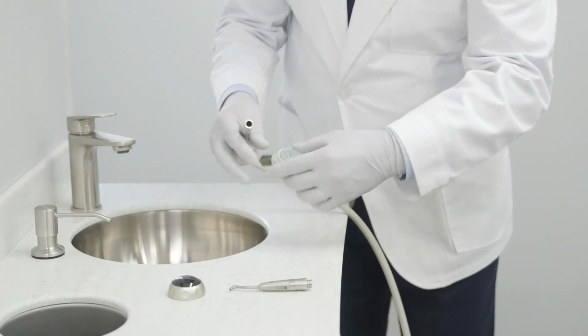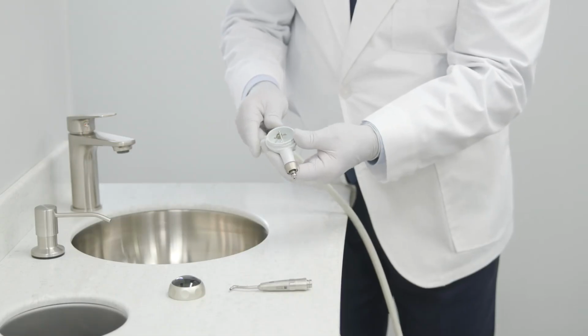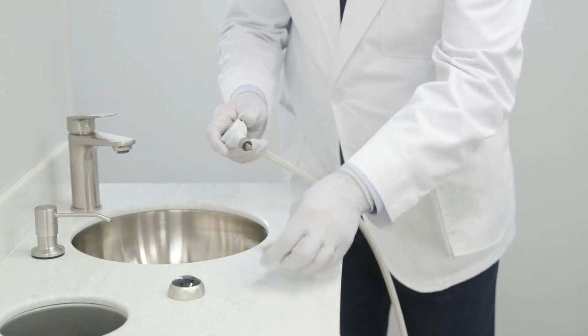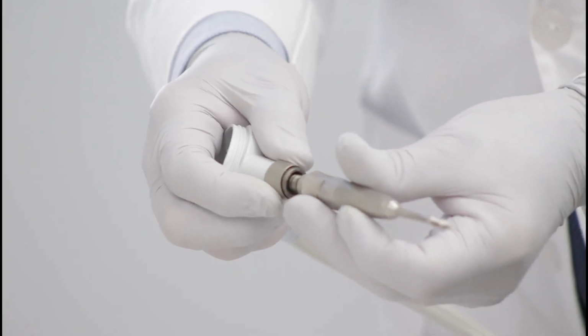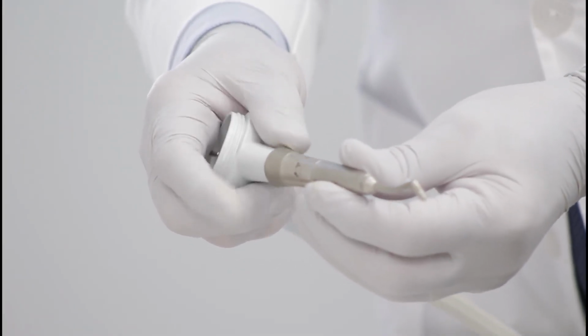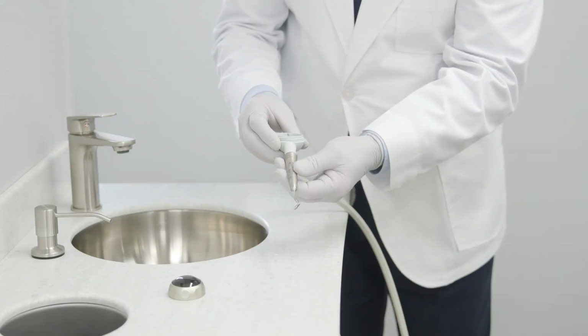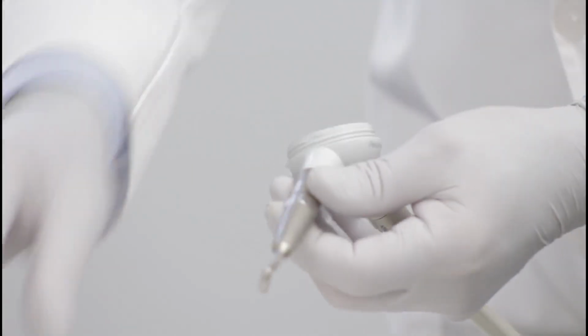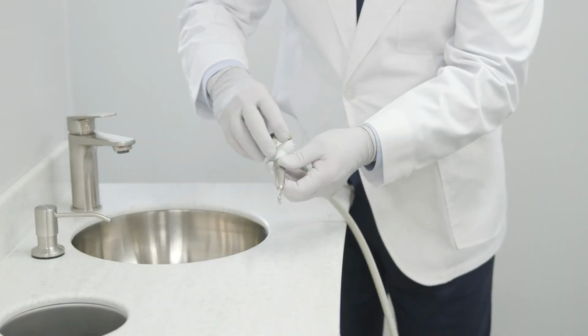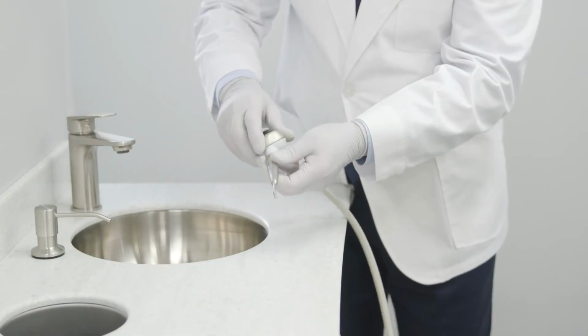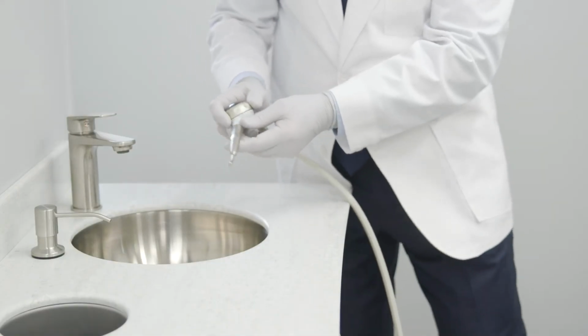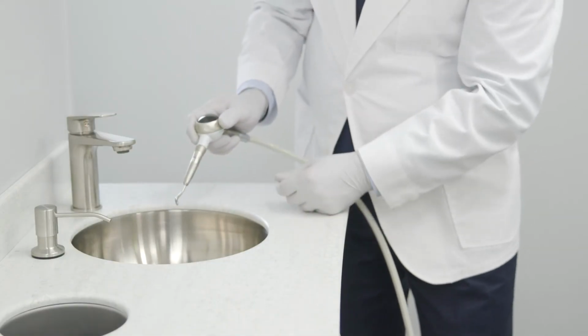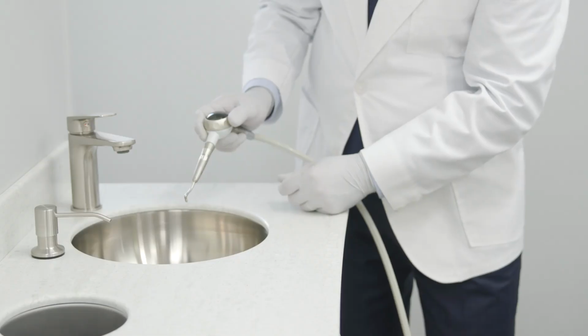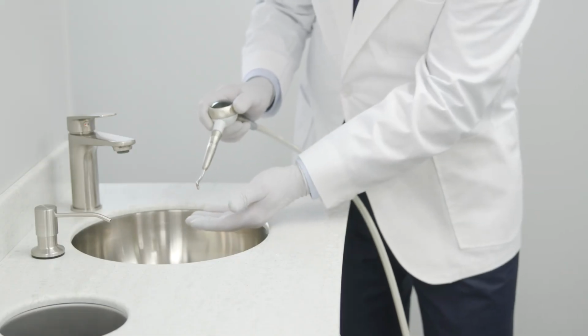To connect the handpiece to the powder case, pull back the handpiece release collar on the powder case and push the handpiece straight onto the connection, and release the collar once the handpiece is in place. Pull the handpiece a little to make sure it's securely connected. Put on the cap and test the handpiece away from a patient before use. If any vibration, noise, or blockage is detected, contact an NSK authorized dealer or NSK service center for troubleshooting.